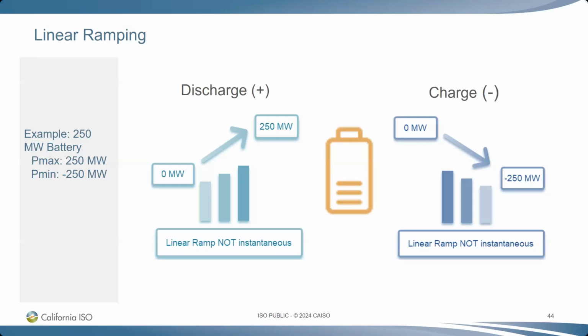But then once it goes live, it needs to be able to follow that as well. So batteries are kind of unique. They can produce full capacity megawatts, and it's like flipping on a light switch. And while that's impressive, because of the way the grid is interconnected and balanced, those linear ramps are required to maintain that 60 hertz frequency, to make sure we're keeping all the connected resources in the grid safe.